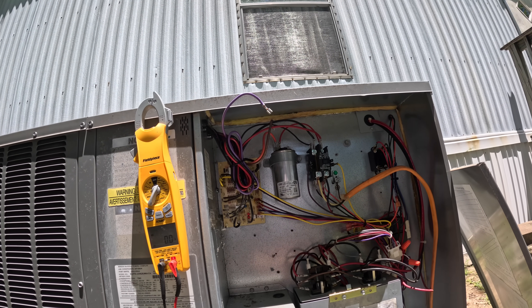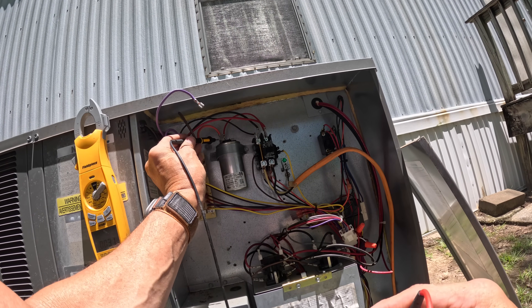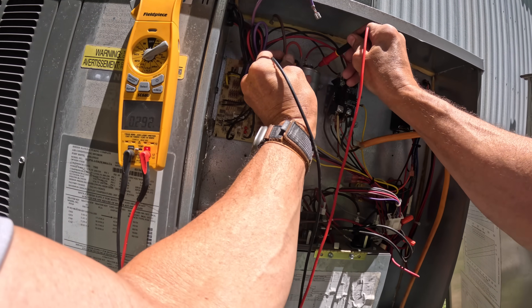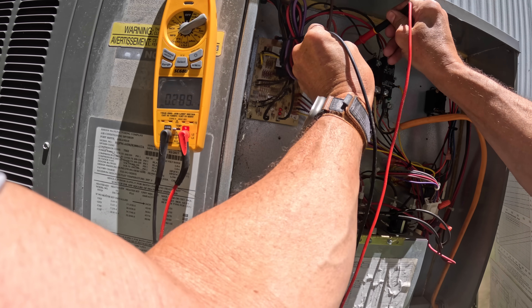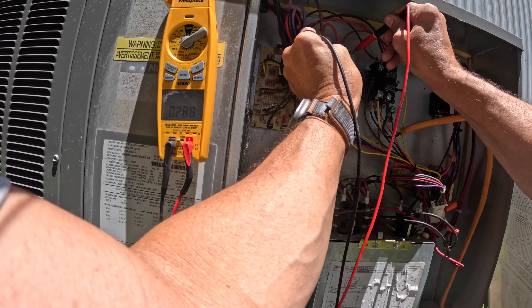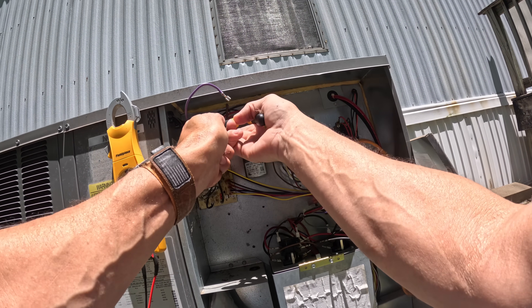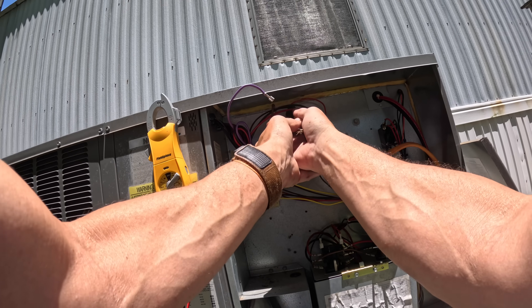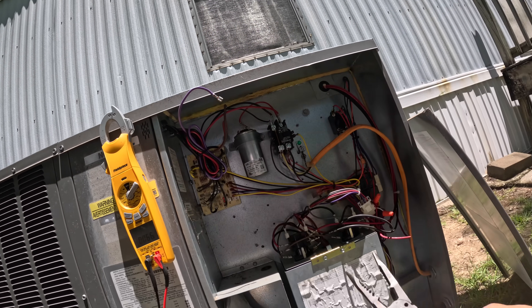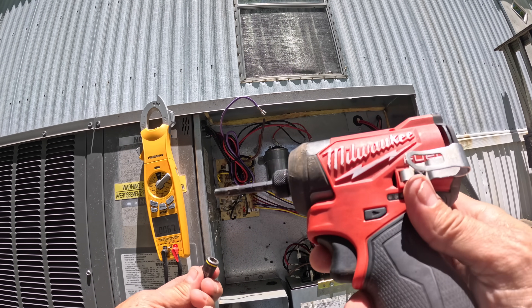It's supposed to be a 40 and 5, so let's check it. This one is the 40 side - reading 0.2 microfarads. And that ain't right.